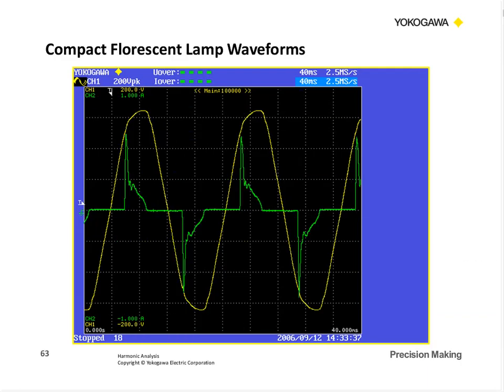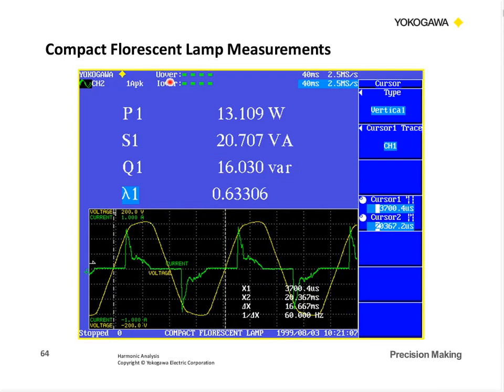Here's another example. This is an old type of compact fluorescent lamp. I like to keep it around because it's got so much noise and distortion to it. So if any of you are in the lighting industry, don't get too upset, because they're a lot better now. But this is an old one, and it had a lot of distortion on that current. So we look at that as an example. Same thing, our power is measured as 13 watts and VA at 20.7, and we had the VAR, and the power factor at 0.633. And a lot of distortion on that current, and that turn-on here distorts the voltage a little bit.